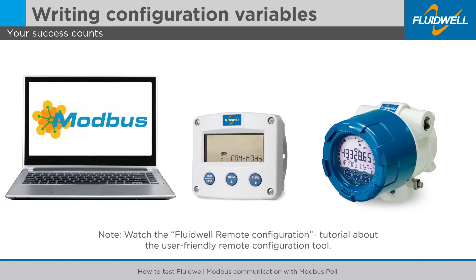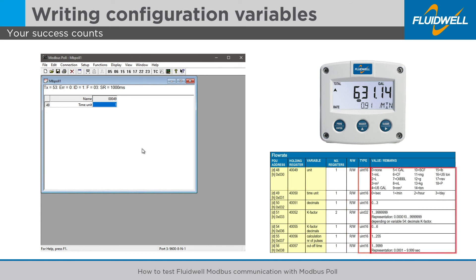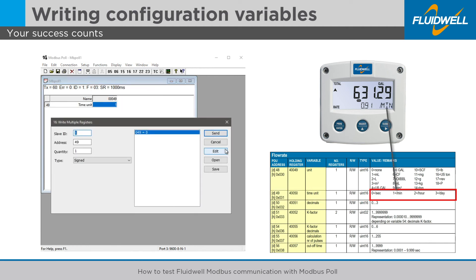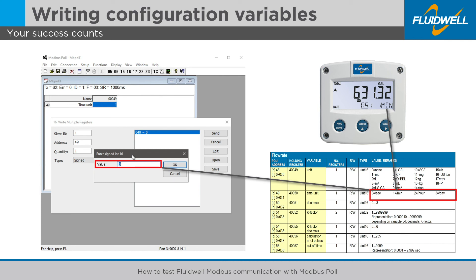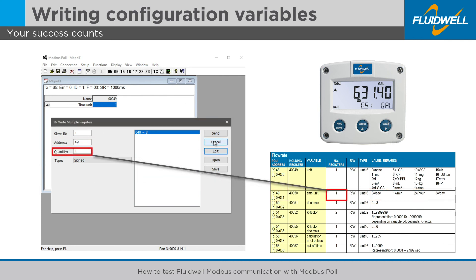Adjusting configuration variables is an easy way for remote programming the product with Modbus communication. Check the configuration variable tables in the manual for a reference of the PDU address, holding register number, variable, number of registers, data type and specific values. To adjust the time engineering unit, use function 16, write multiple registers. Write a value of 3 for a time unit per day to PDU address 49 in an unsigned single write action.